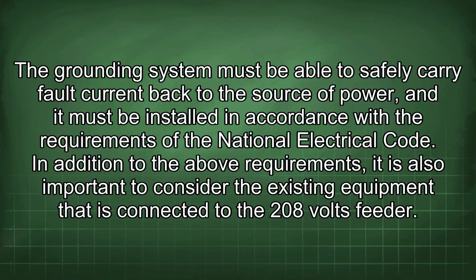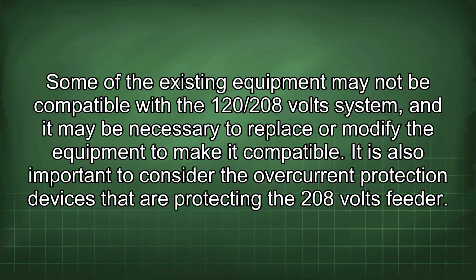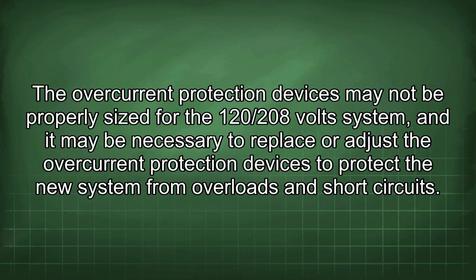In addition to the above requirements, it is also important to consider the existing equipment that is connected to the 208 volts feeder. Some of the existing equipment may not be compatible with the 120/208 volt system, and it may be necessary to replace or modify the equipment to make it compatible. It is also important to consider the overcurrent protection devices that are protecting the 208 volts feeder. The overcurrent protection devices may not be properly sized for the 120/208 volt system, and it may be necessary to replace or adjust the overcurrent protection devices to protect the new system from overloads and short circuits.